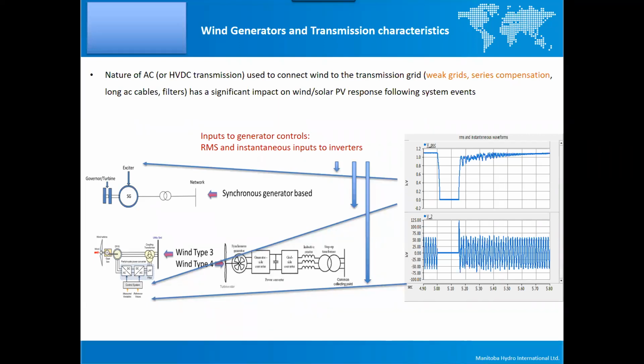It's not an instantaneous natural response. You still have to figure that out, the measuring system will have to figure it out. So there is a delay. And if you can keep that delay as short as possible, maybe a few cycles, then the synthetic inertia would help your system stability. In some other cases, you probably really need the support from a synchronous machine, because that delay may be the difference between stability and instability.